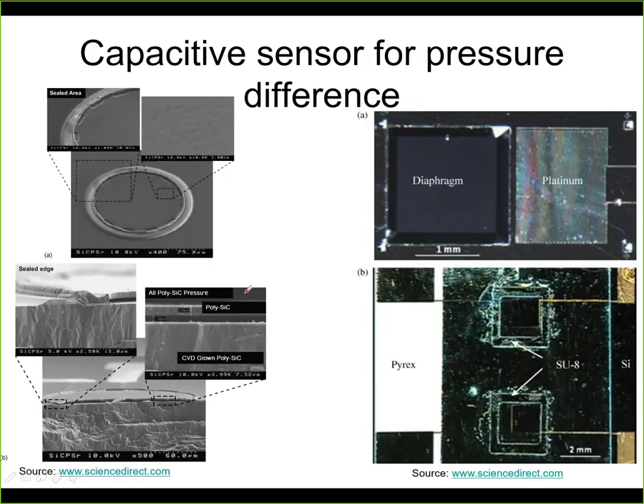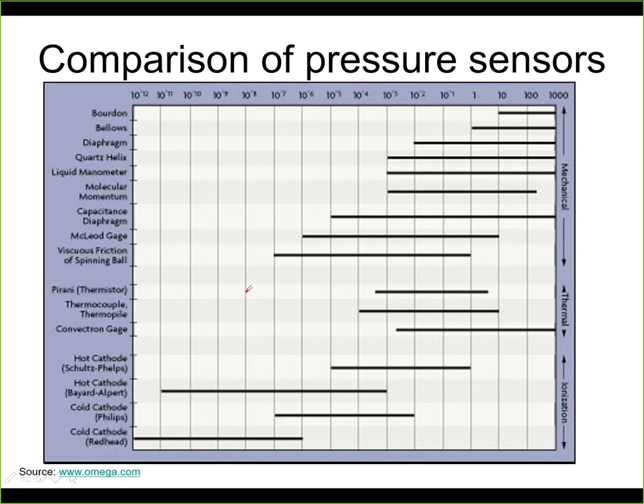And now at the end, let me compare different pressure gauges. We have seen only some of them that are here in the table. We have seen the Bourdon element here today. So typically this is the pressure where it can work. So it can work for larger pressures. So if you are looking for something like 10 kilopascals or 1 megapascal, then the Bourdon element is a good choice if you don't need an electrical output.